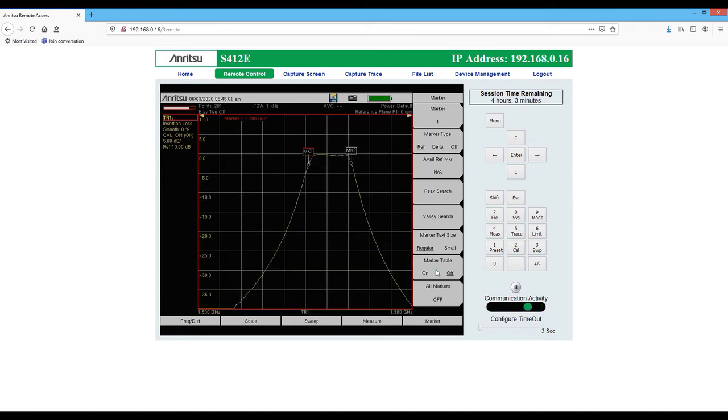And what we're going to do is we're going to change over. These are the field measurements that you've seen. All of this is the field measurements. Very similar, almost identical to your typical site master. The differences are number of data points and the fact that if I tried to change frequencies right now, it would warn me that I was going to lose my calibration.